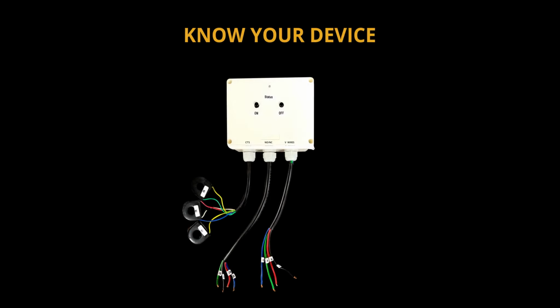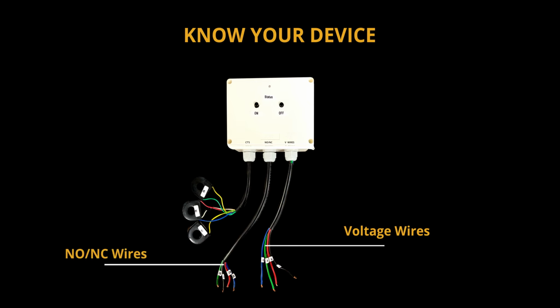On the device, power module, you can see the positions marked as V wires, that is the voltage wires which will be connected to the contactor. The NO-NC wires on the power module will be connected to the NO-NC terminal on the motor panel. CTs refers to the current transformer that measures the current consumed by the motor panel. The on-off button on the power module will help you control the device manually.